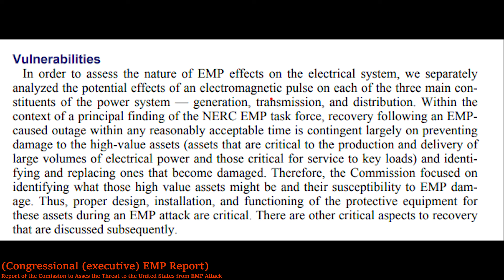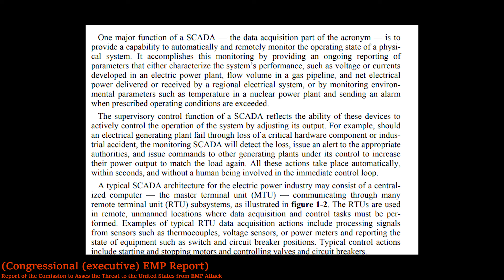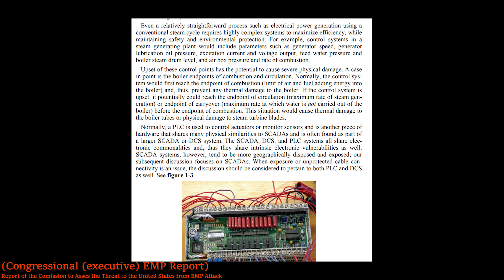Even a simple safety shutdown can often require hours or even days to bring the system back to operational levels. An example cited was a basic industrial pressure boiler. When the system gets soft-killed, even for a short time, it's likely that the pressure would increase drastically as the process is temporarily no longer controlled, and the SCADA and its backups would either be offlined or desynced, unable to correct for the spike in thermal output. Best case scenario, the device has to self-shut down. Worst case scenario, complete destruction of the system, despite all of the electronics functionally returning to nominal order very shortly after.